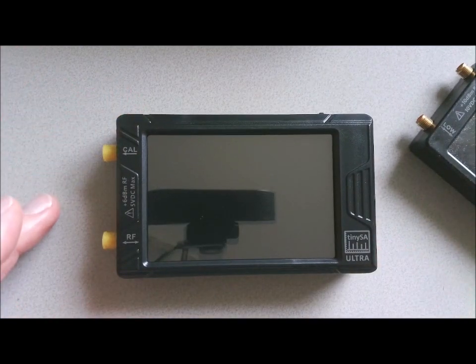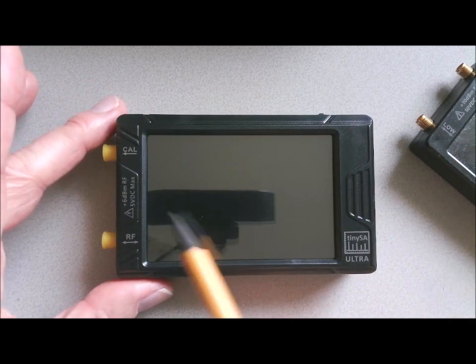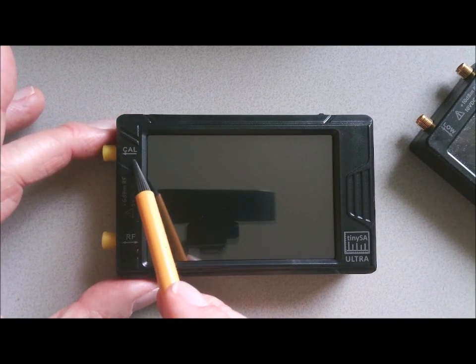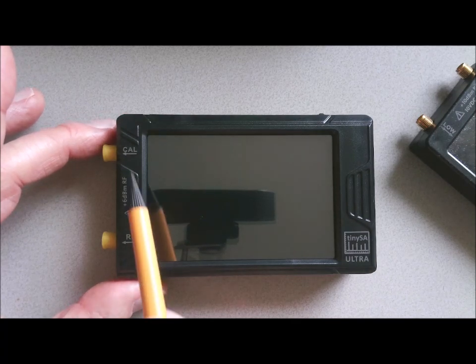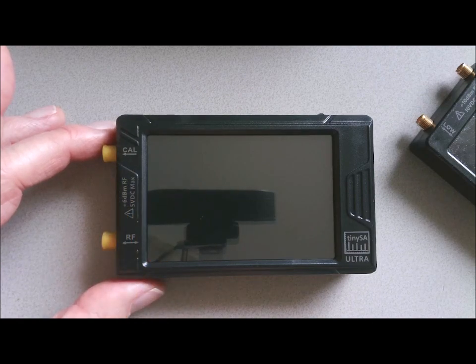What is different? If you look to the outside of the box, you can see that the ports are denoted here in a different way. There's no longer a high and a low, but you have only one RF connector and you have the calibration connector.